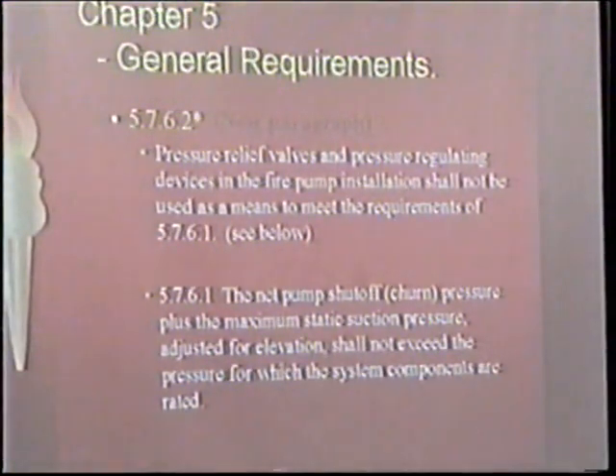And so that was kind of the little avenue we had, I think, before, that if you couldn't put a relief valve in there, you could maybe put a regulating valve in to keep the pressure lower in the system. And they don't allow you to do that in the fire pump discharge piping. That's the piping from the discharge flange to the control valve. That's the way I interpret that. I don't know if anybody else sees that differently or not.